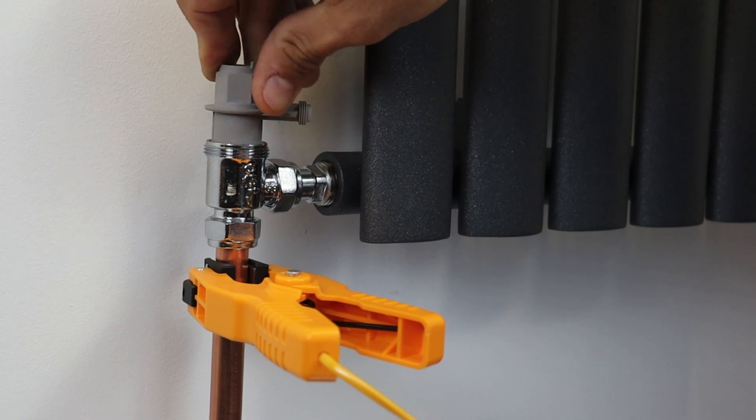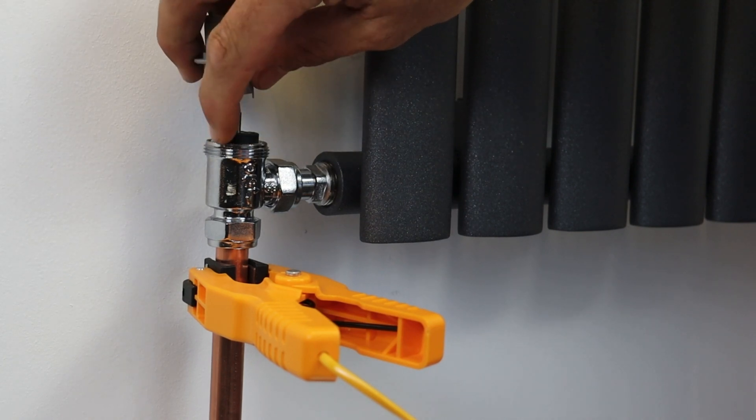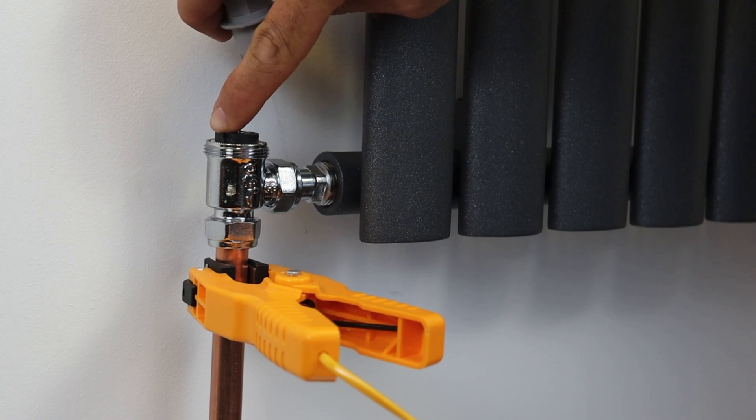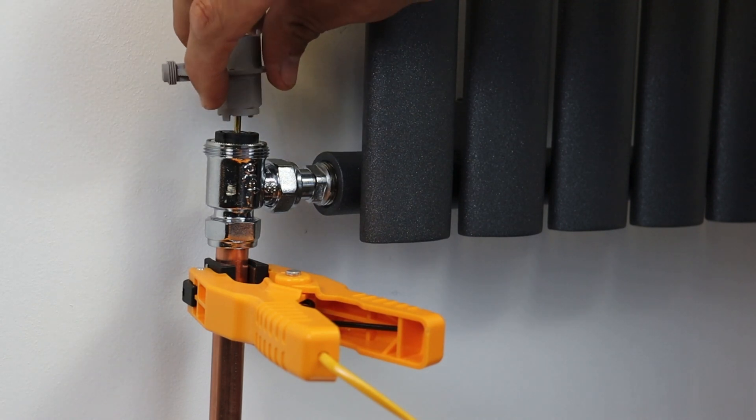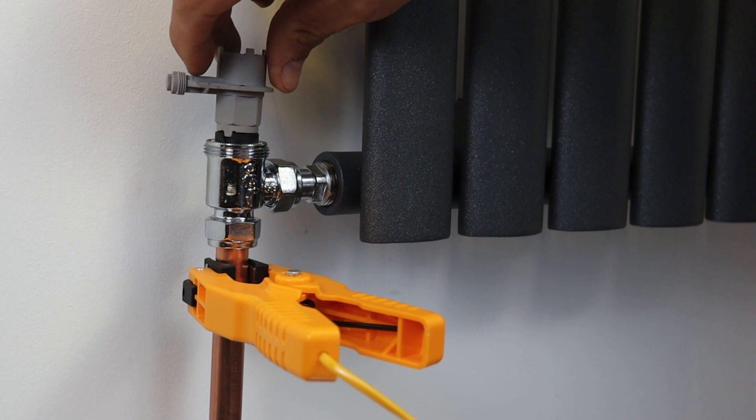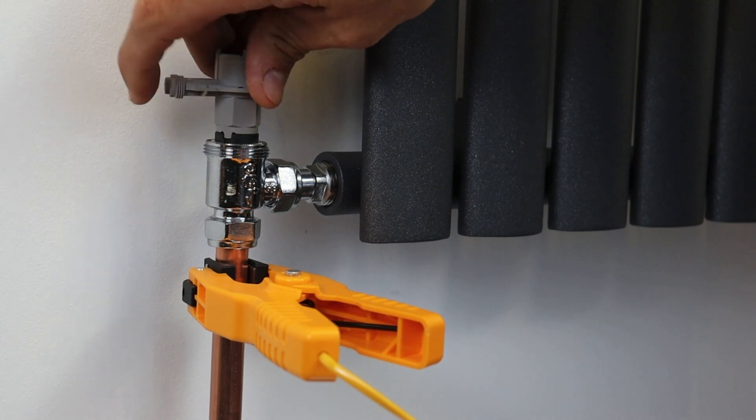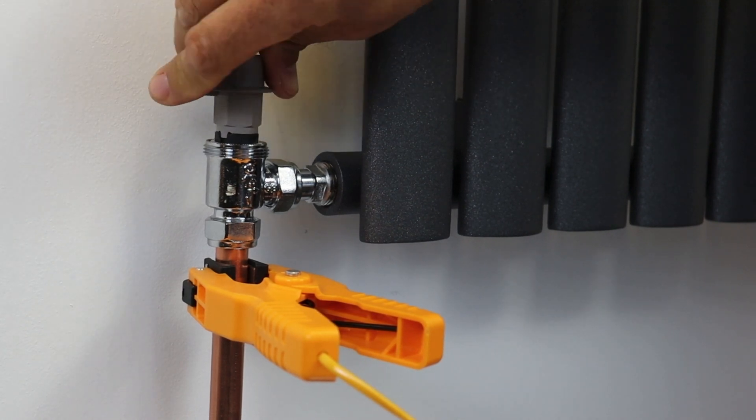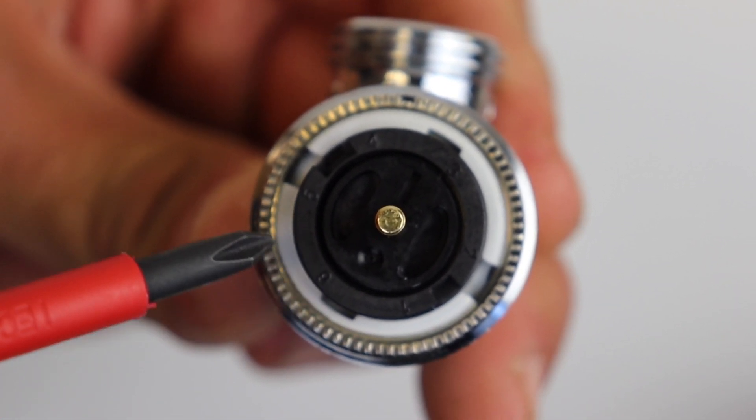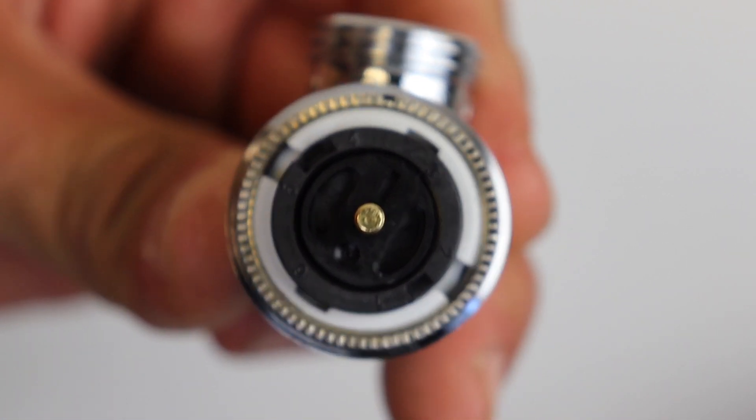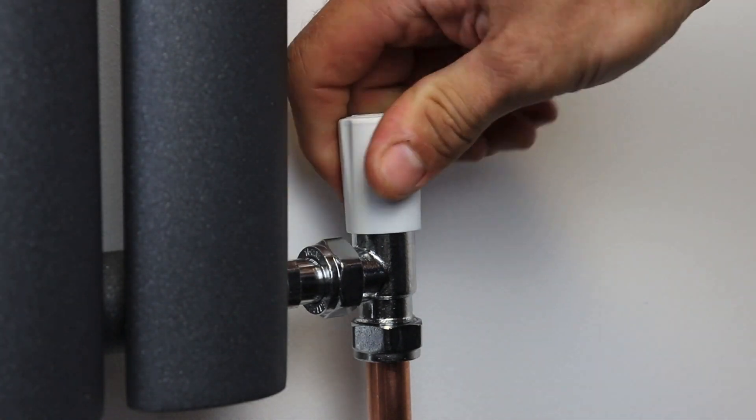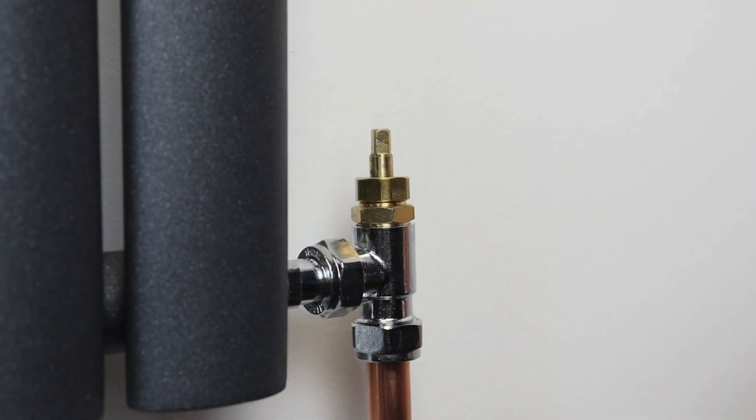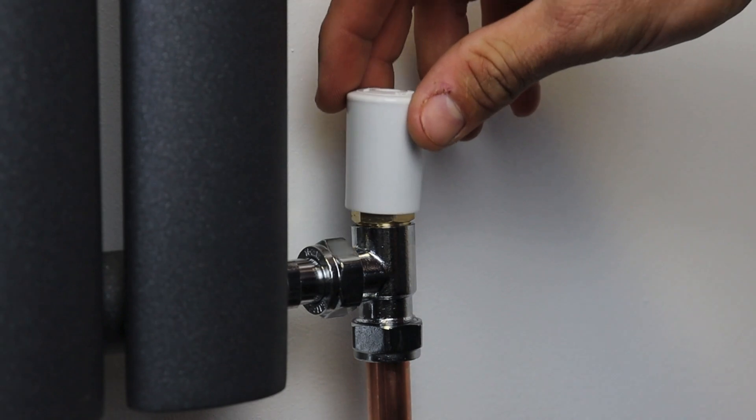Give it half a turn. Now it's important you don't take that clamp ring all the way out otherwise there's nothing holding the insert in. Once that is loosened flip the key over so it fits the other way around and this will then allow you to turn the valve insert in a clockwise direction to one of the six valve presets. When using this method it's important to remember to leave the lock shield wide open but still lock it off to prevent any future changes.